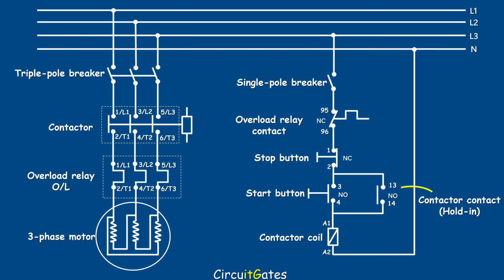On the starter circuit diagrams, we have main labelings. Firstly, there are contacts labeled normal open or normal closed. This refers to the state in which the contacts will be when the electric motor is off or when it is not energized. Secondly, there are numbers printed on starter components. These numbers help when installing a direct online starter.